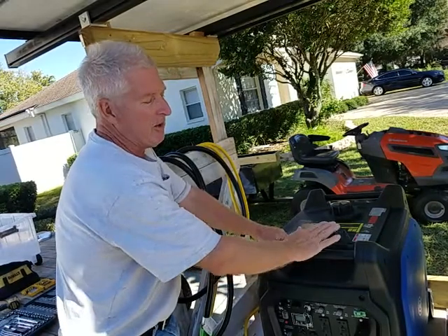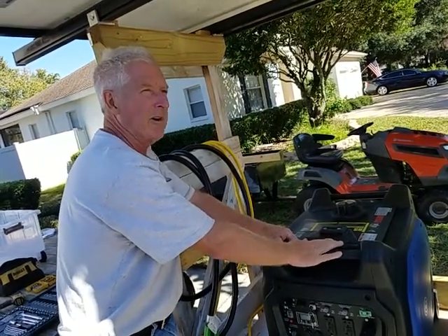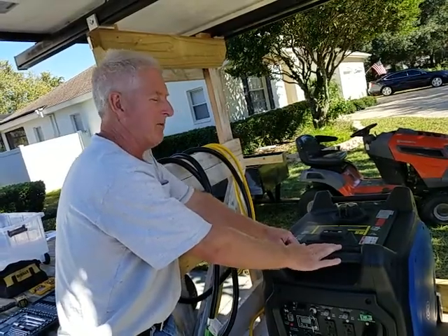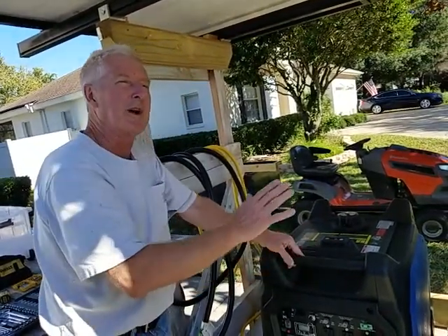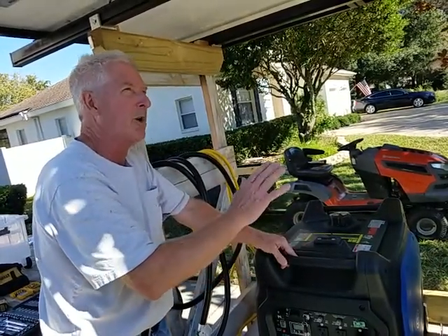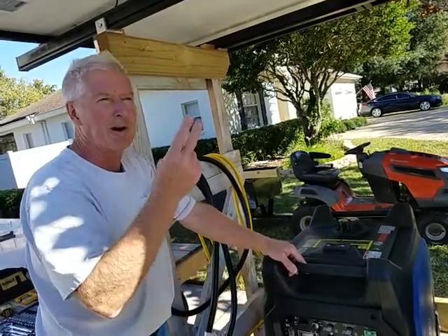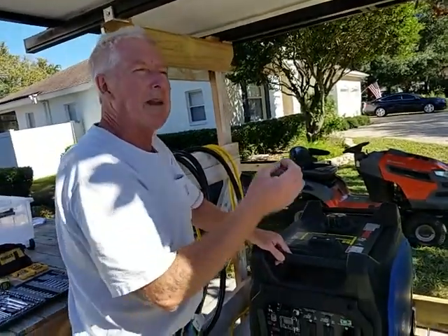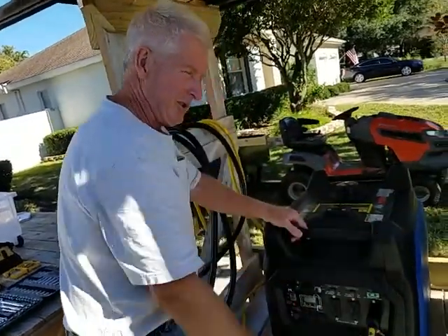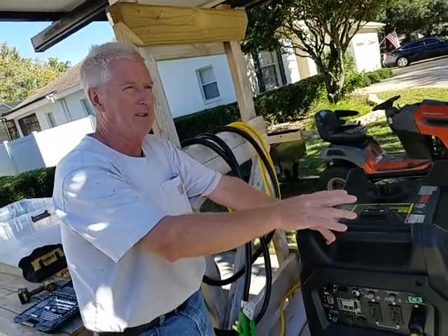So instead of this generator running 24 hours at fractional load, very inefficiently, polluting the environment, we're going to have less pollution because we're going to run it where it runs very efficiently, the lowest emissions per kilowatt hour of power generated. We're going to run it for 2 hours potentially instead of 24. Charge the batteries, and that becomes like a hybrid. And now the old diesel-electric hybrid thing. Correct. The energy storage device is providing that buffer for us, okay?